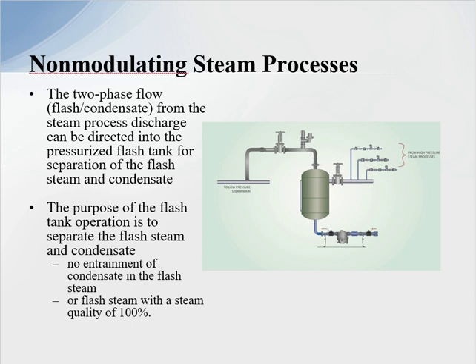Two-phase flow — flash steam and condensate from the steam process discharge — can be directed into a pressurized flash tank for separation of the steam and the condensate. Here we have high pressure or non-modulating loads from a process directed into this flash tank. The flash steam is separated from the condensate and delivered into a lower pressure system. The separation of flash and condensate allows no entrainment of condensate, giving us 100% steam quality coming out of the flash tank.